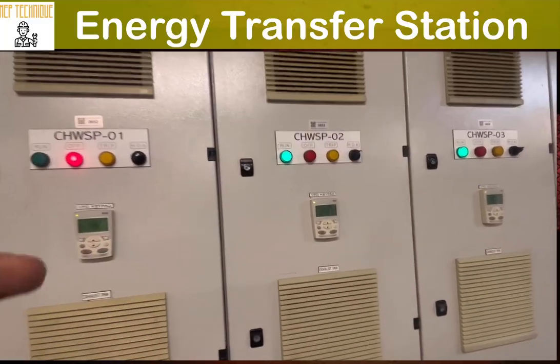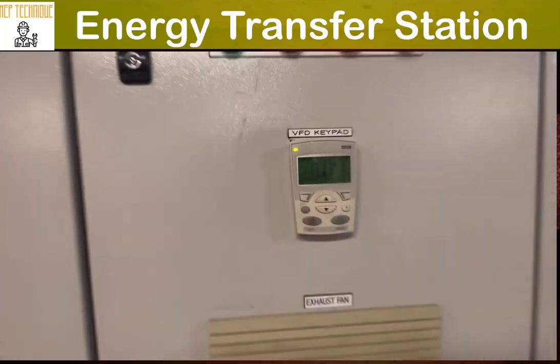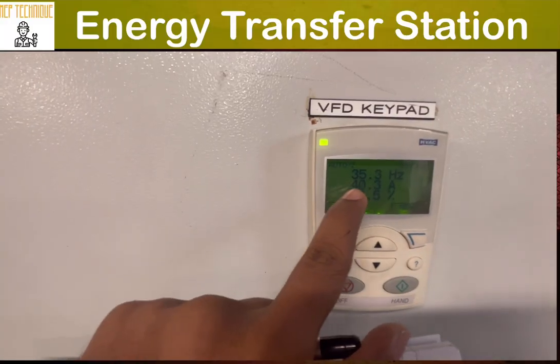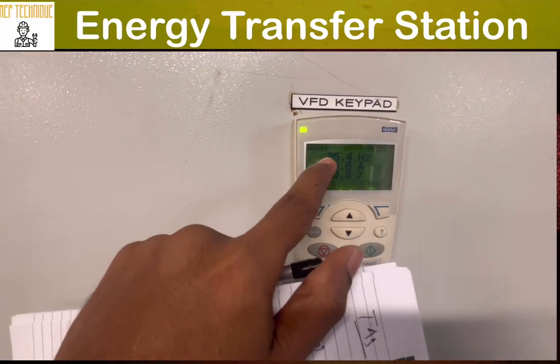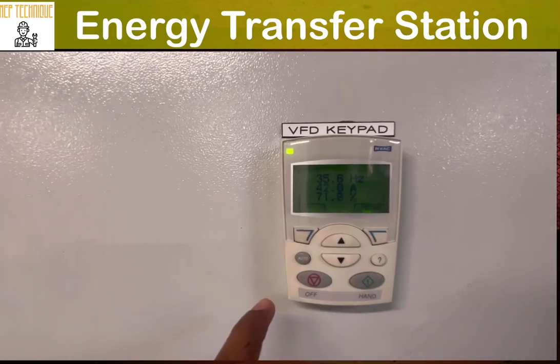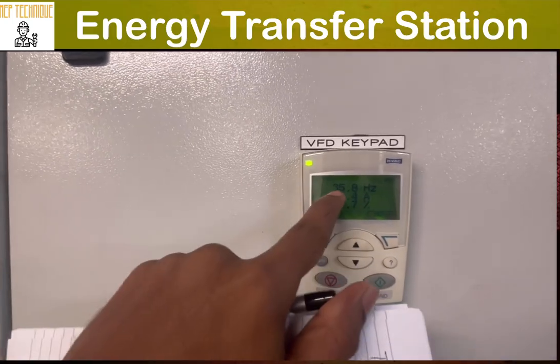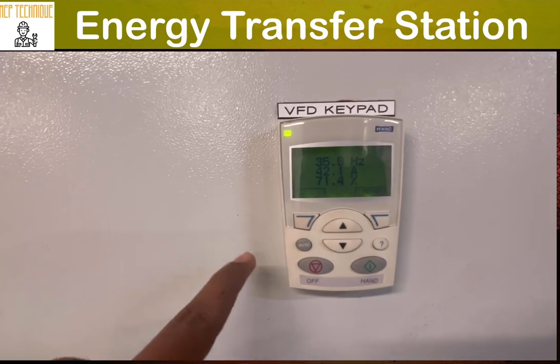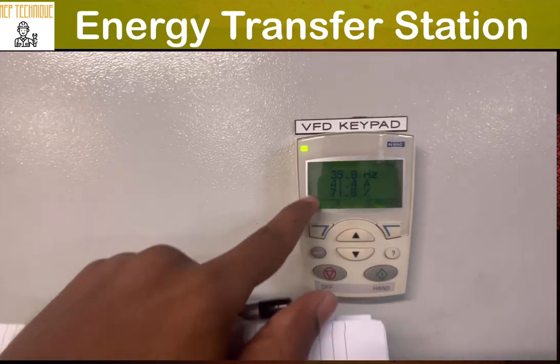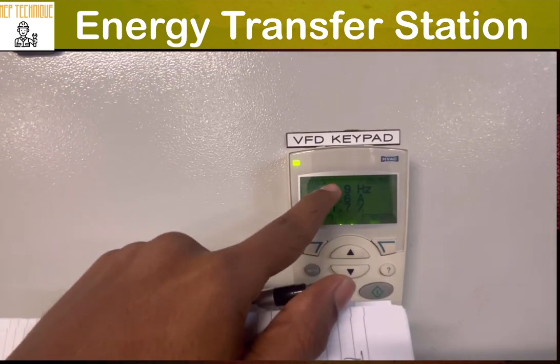When the differential pressure decreases, the VFD will be ramped down. You can see the frequency is varying. That means it depends upon the differential pressure across the chilled water supply and return line. When the differential pressure increases, the frequency will increase. When the differential pressure decreases, the frequency will decrease.